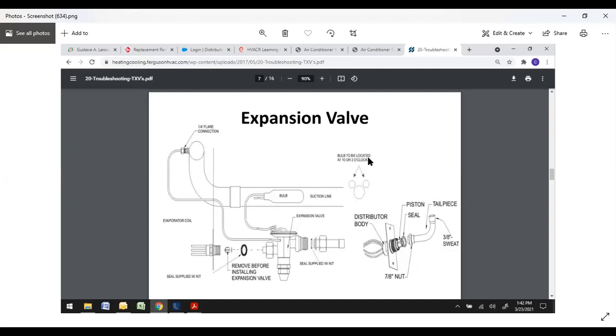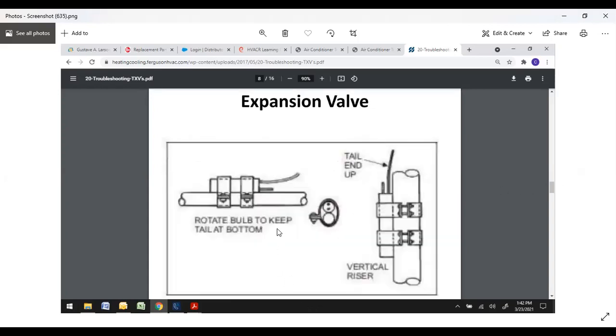Make sure your bulb is secured. Ideally, you want to use a 10 or 2. This is a side view, so you want to do 10 or 2. Don't mount on the bottom. You will get incorrect readings. So what they're saying here is if you're going to mount horizontal, what they're recommending is a 10 and 2 with your pigtail closer to the bottom. If you have to do a vertical, that's fine. Make sure your pigtail is pointing up.